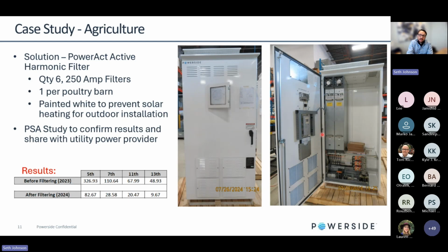And so our design from an active filter standpoint is a modular design. Each of these modules is rated at 125 amps. So of course, 2 of them together makes 250. And then we have space for 2 more. If we ever need to in the future, we can add 2 more modules to give them up to 500 amps of harmonic correction. So the utility, after the client installed the active filter, wanted a report.